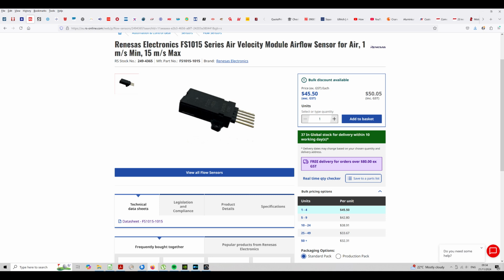Now, the other one you will see coming up in the video is an air pressure sensor or differential sensor to check for the restriction of air going through the radiator. So we'll have a tube to the inlet side of the radiator, and then the other tube would be to the outside or ambient air of the radiator, to see if there is a difference in airflow through the cores.